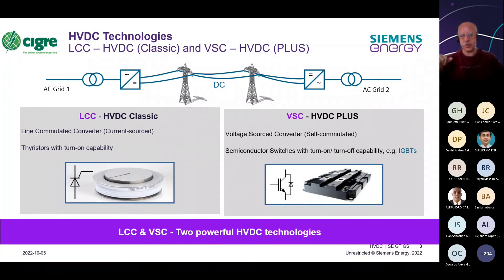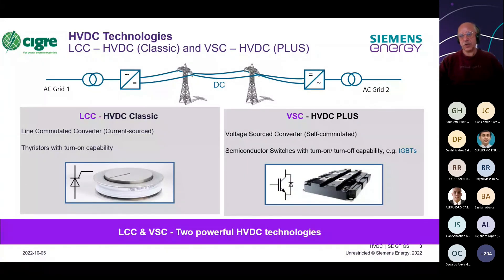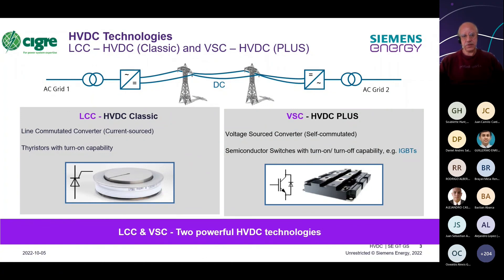In LCC, voltage polarity reversal is achieved either by changing the firing angle of the thyristors or by using polarity reversal switches. This creates complications in multi-terminal schemes, which require special polarity reversal switches. For point-to-point connections, however, power direction can be simply changed by adjusting the firing angles, without needing polarity reversal switches.